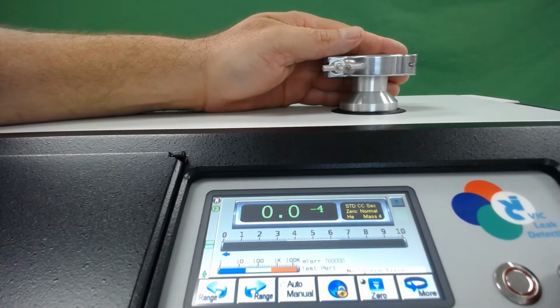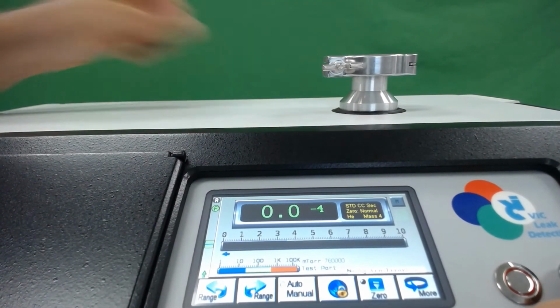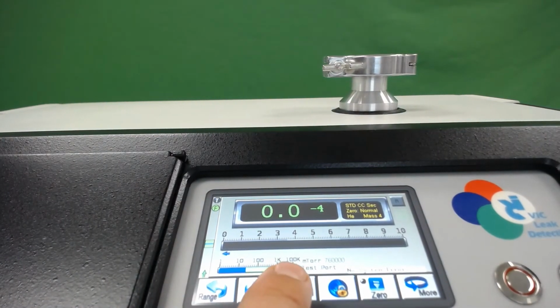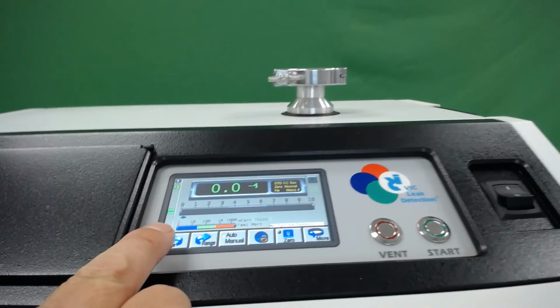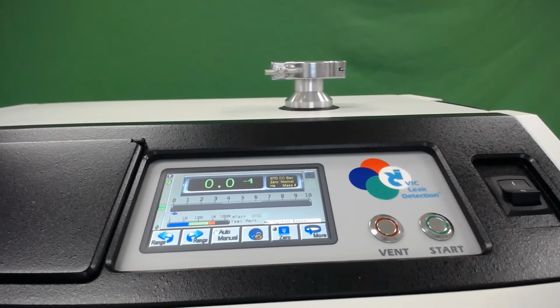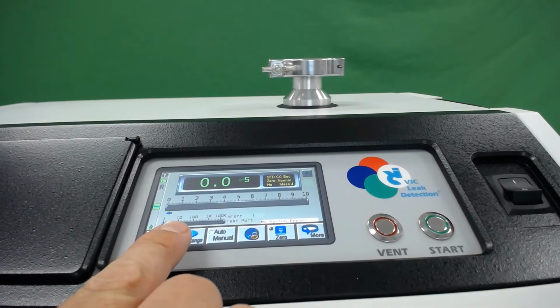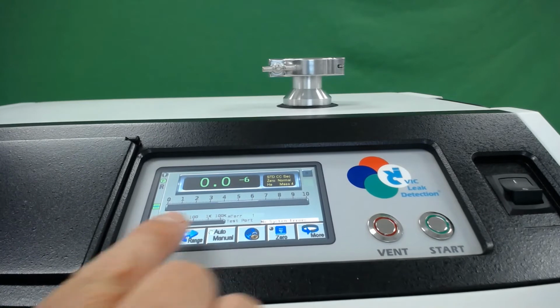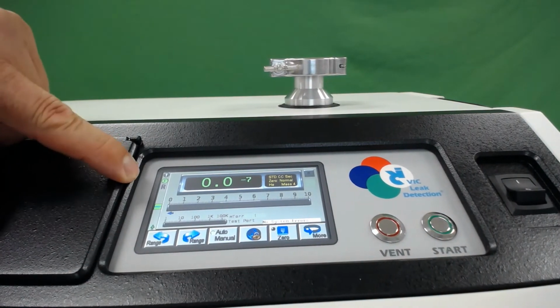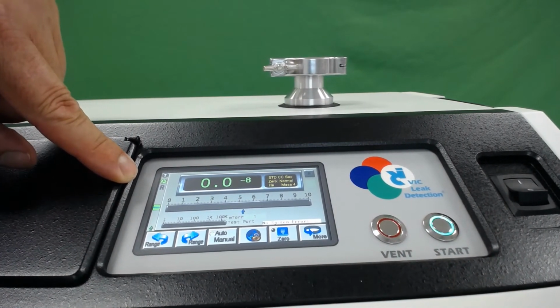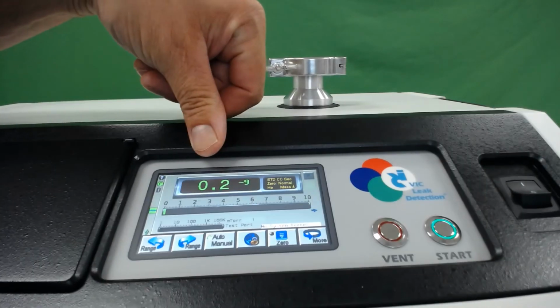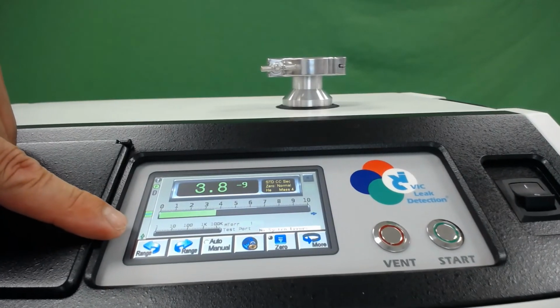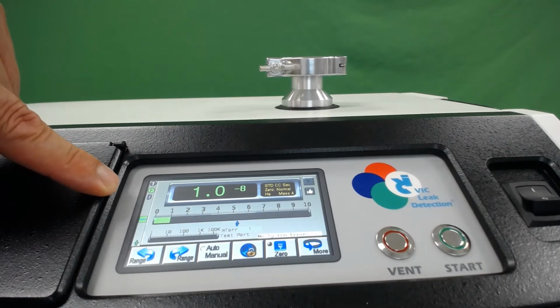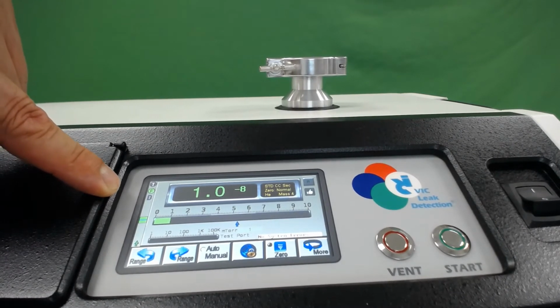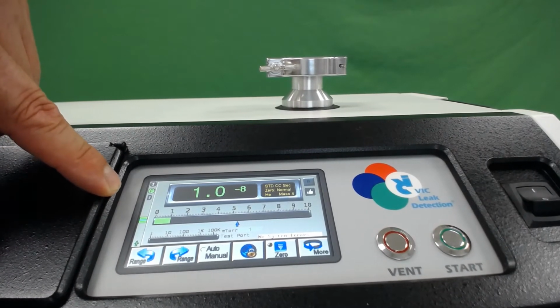You can initiate a cycle by pressing the start button. The test port will begin to evacuate. Once the machine reaches the required vacuum pressure, we begin testing. Right now, the R is indicating that the machine is in reverse testing mode in the 10 to the minus 8, and because the vacuum level reduced further, we entered the direct testing mode, which provides 10 to the minus 9, 10 to the minus 10 leak detection.